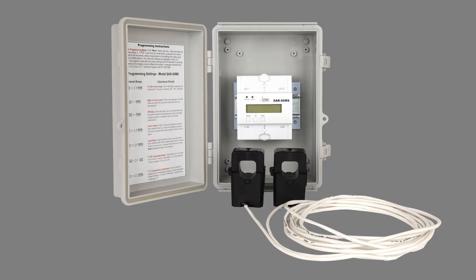The SAK60MS is a peak shed device intended to shed loads that exceed the load calculation of a service or panel in accordance with NEC 2023 Article 220.70.